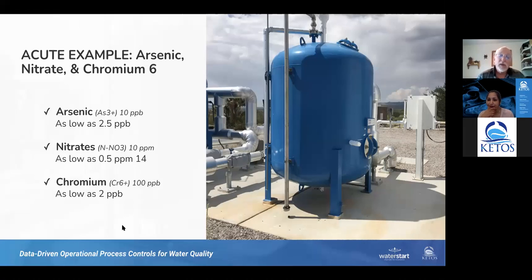Right, and it becomes more critical as the levels climb in these wells, getting closer to the 10 parts per million range. So are you going to shut down a million dollar well because you can't monitor the nitrates? You wouldn't want to. You could set an alarm saying if this approaches 9 parts per million, shut it down, and it could actually be almost automated through the SCADA system. That's not a compliance sample, but it's an operational decision sample that's incredibly valuable.